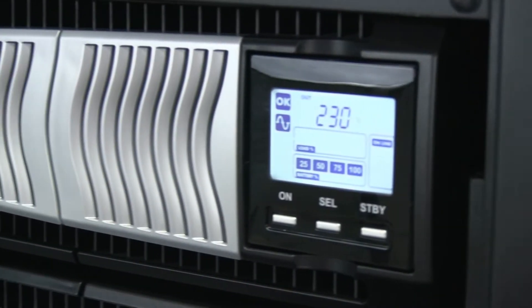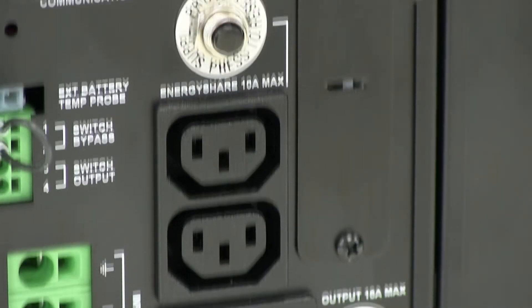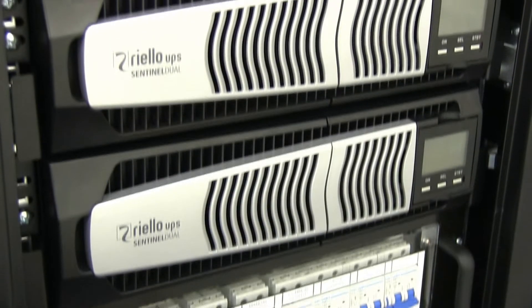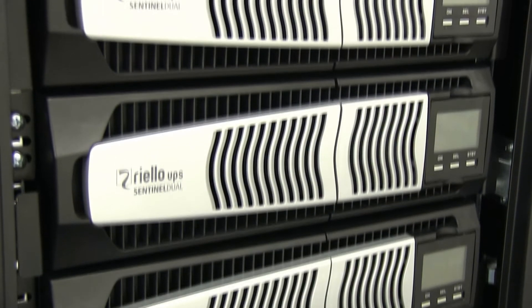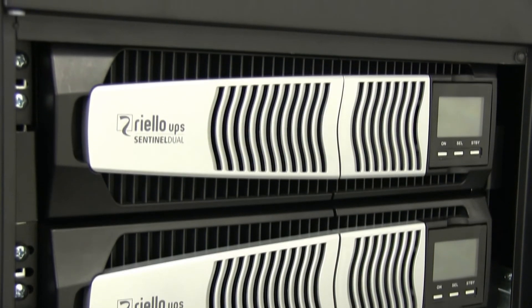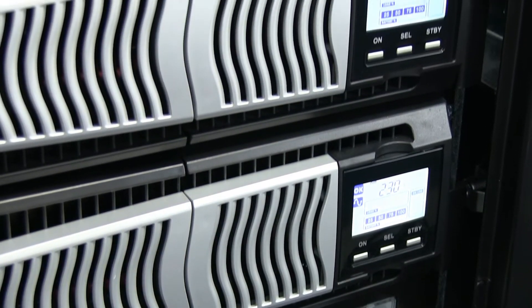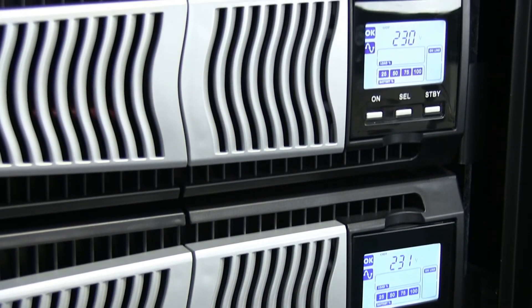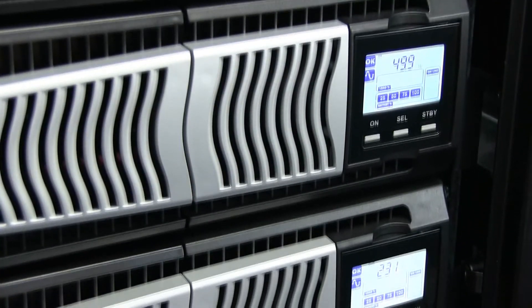With Sentinel Dual, it is possible to parallel multiple units to achieve a greater power capacity or to add redundancy to critical power installations. Paralleling up to 3 Sentinel Dual UPS units allows the user to create the highest density rack-mounted UPS installation currently available, at 30kW capacity or 20kW N+1.